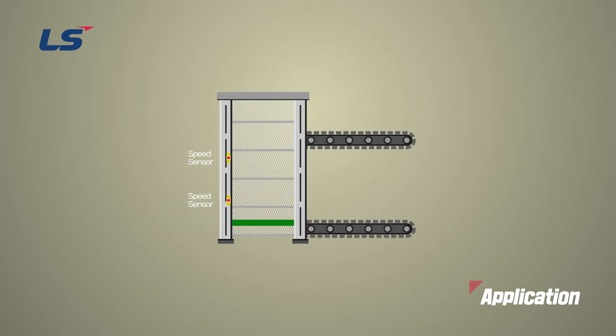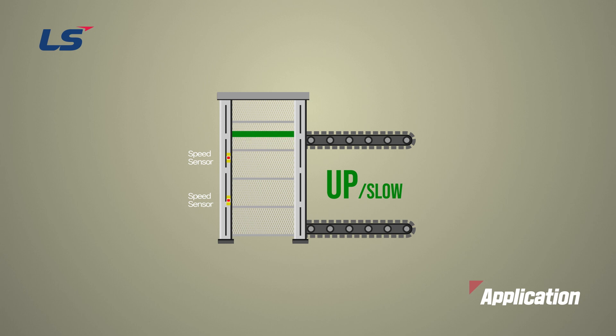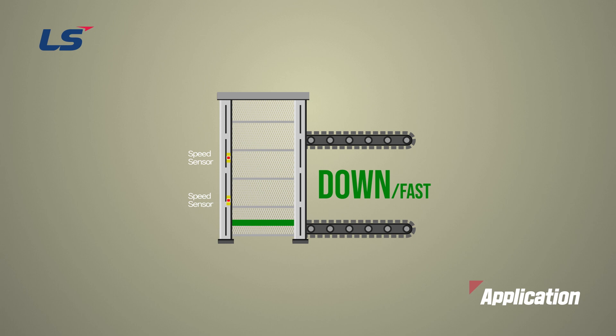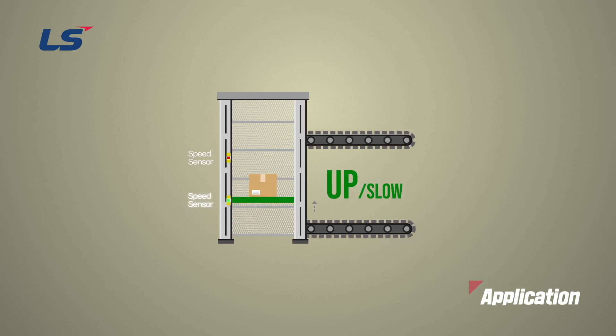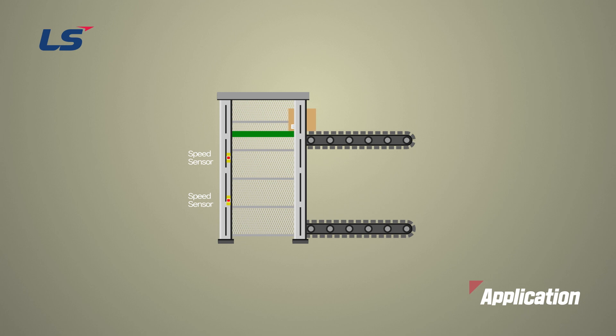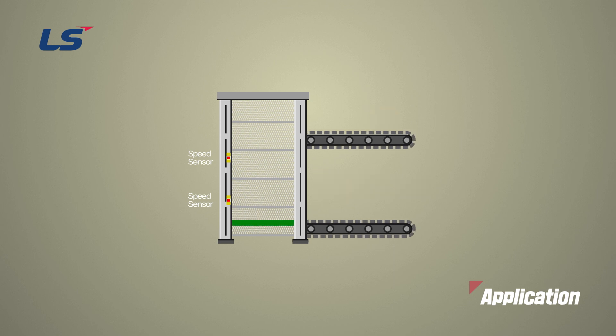Lift equipment carries the load of the automation line and moves back and forth, up and down. When first started, it operates at high speed, and when nearing the stopping position, it operates at low speed and then stops. The acceleration-deceleration time can be set differently for rising versus descending — slow acceleration-deceleration when items are loaded on the pallet, and quick response when it's empty. The speed changes as the contact signal from the pallet sensor is input to the AC drive.